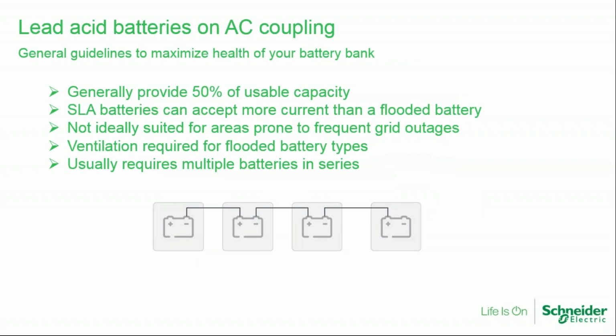Lead acid batteries, you need to follow the general guidelines. We discharge them to 50%. We keep the current within their specified amount. They're not good for partial discharge. And obviously, you need to ventilate them, someplace for the gas to go, and they generally use multiple batteries. Generally, you use 6-volt batteries, so you put 8 of them in series.